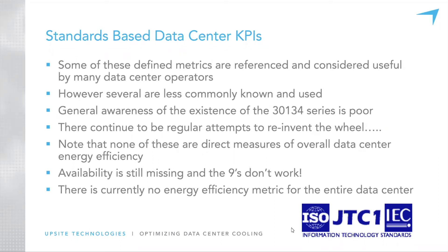Worth noting that none of these measures are direct measures of overall data center energy efficiency — we're still missing that. From a pure physics perspective, energy efficiency needs to reference useful work done. At the moment we have no way of measuring the useful work done in a data center. There are proxies we might use, but in a very pure sense — ordering electrons or converting electrons to photons and back again — defining that as useful work done is very difficult, which is why we still don't have a single energy efficiency metric for a data center as a whole.